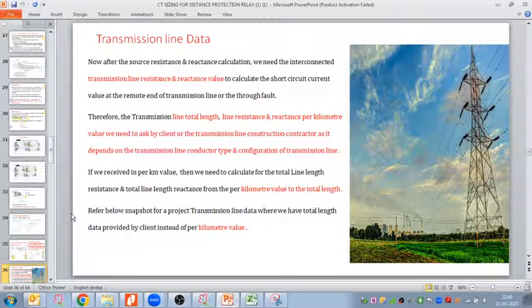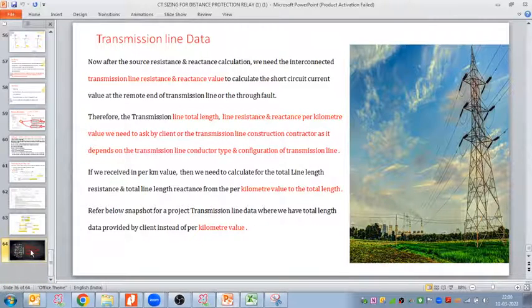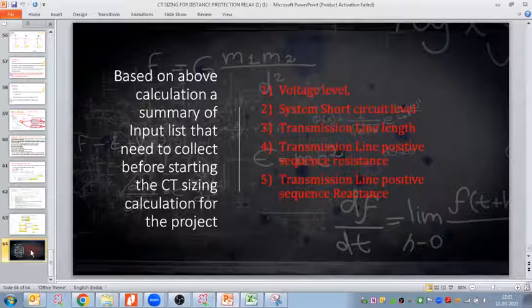Along with these calculations I am also making a list. Whenever your project manager asks you to do the CTVT sizing calculation, what will you ask them before starting? The voltage level, and from the tender you know the system short circuit current. Then the transmission line length, and the transmission line positive sequence resistance and reactance. Why not the negative sequence resistance and reactance? Because for any static system, the line positive sequence resistance and reactance is equal to the negative sequence resistance and reactance, so you don't need the negative sequence.